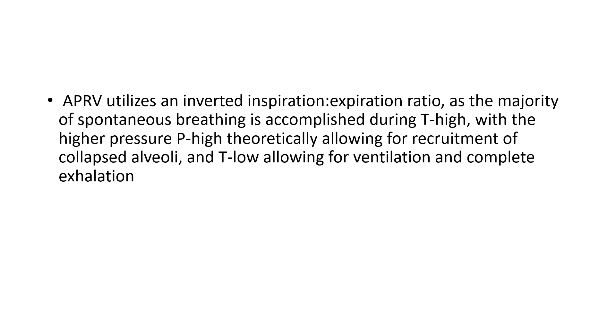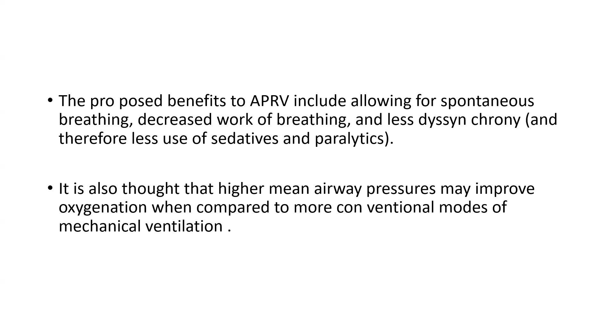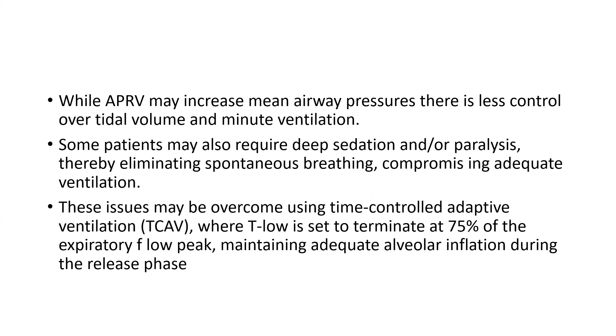The proposed benefits of APRV include allowing for spontaneous breathing, decreased work of breathing, and less dyssynchrony. It is also thought that the high mean airway pressure may improve oxygenation when compared to more conventional modes of mechanical ventilation. While APRV may increase the mean airway pressure, there is less control over tidal volume and minute ventilation, and some patients may also require deep sedation or paralysis, thereby eliminating spontaneous breathing and compromising adequate ventilation. These issues may be overcome using time controlled adaptive ventilation, where T low is set to terminate at 75% of peak expiratory flow, maintaining adequate alveolar inflation during the release phase. If the patient requires high minute ventilation, T high is reduced to increase the frequency of release, while the T low remains set based on the expiratory flow dynamics.